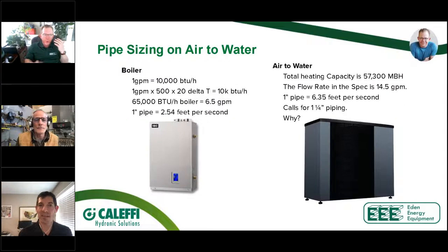So the length would change to the same length as the 12-inch example, and then it would come back to that same number. Yeah. So one of the things we're just going to touch on as we keep moving here is, we want to make sure we don't take too much of everybody's time, is the other thing to pay attention to is pipe sizing. So the pipe sizing on air to waters is not the same.